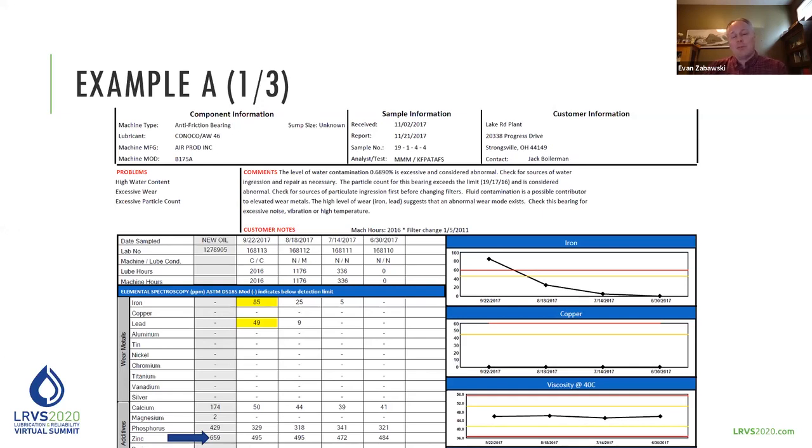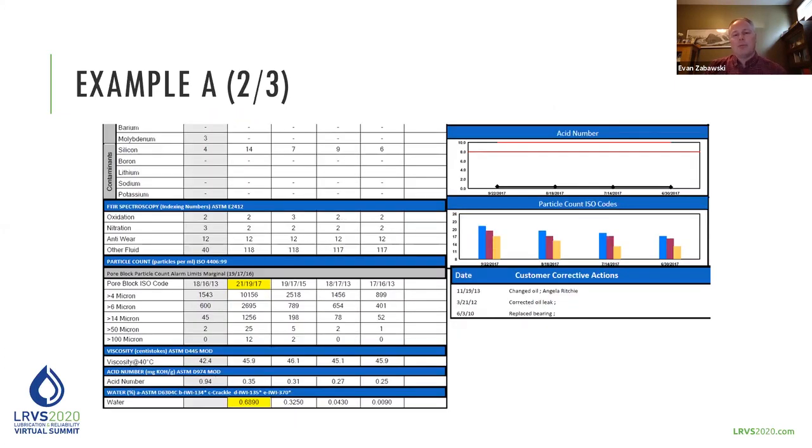So on this first half of the report, I've identified iron and lead as effects. I haven't found a single cause yet. So keep going down the report and keep looking for something. Just, again, be methodical. And the next thing I see that I don't think matches trend or doesn't match new oil values very closely, silicon. So silicon a cause or effect?